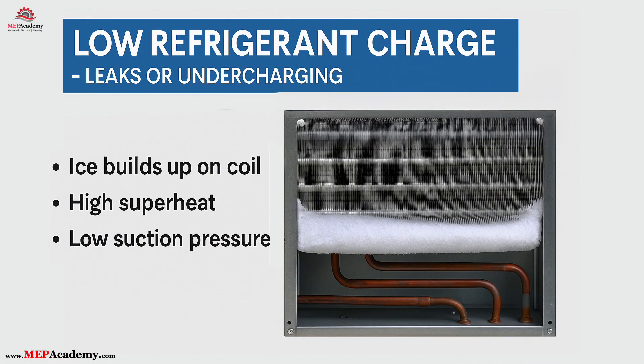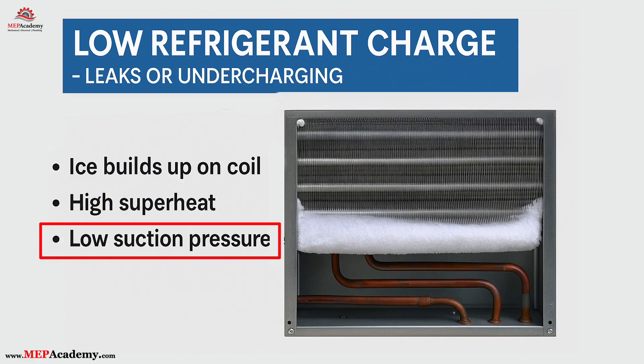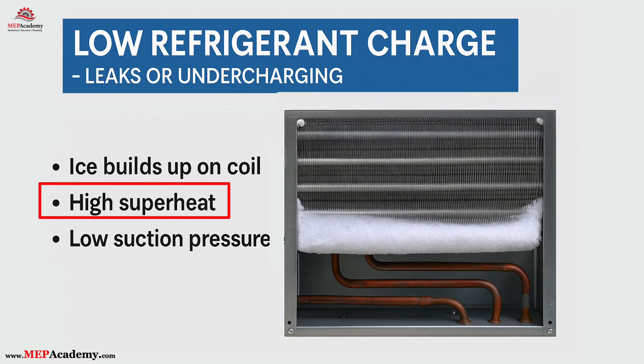Number three: low refrigerant charge — leaks or undercharging. A low charge condition reduces system efficiency and can result in coil icing and compressor overheating. This often stems from small leaks over time or improper charging during service. Common signs: low suction pressure — because there's insufficient refrigerant evaporating in the coil, resulting in less vapor returning to the compressor. High superheat — because there isn't enough refrigerant to fully saturate the evaporator coil, so the remaining vapor continues to gain heat, raising the superheat temperature.